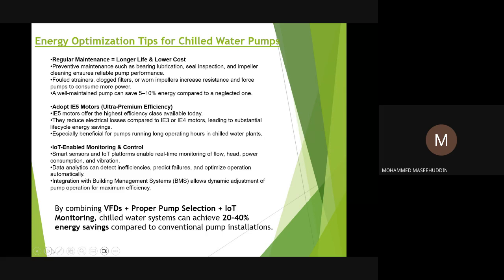So by combining all these above factors like VFDs, the proper selection of pump, and IoT monitoring, chilled water systems can achieve about 20 to 40% energy savings compared to conventional pump installations. So it means, guys, if you are spending 100 dirham for this pump today, you'll be spending only 60 dirhams for the same pump by utilizing all these things.